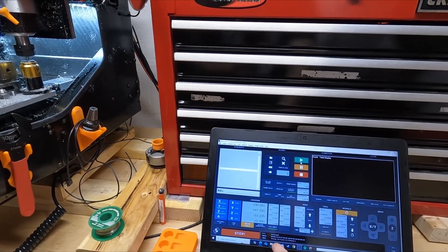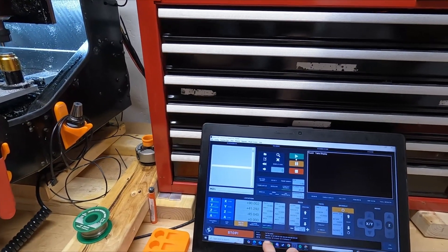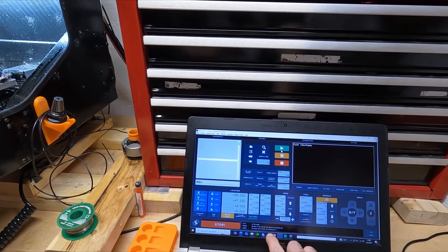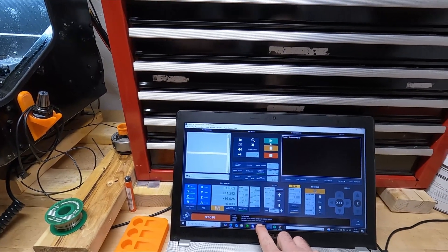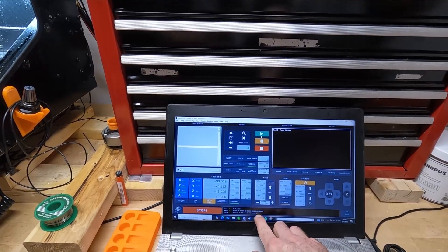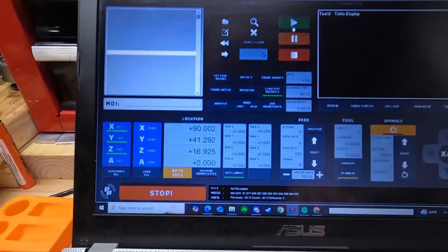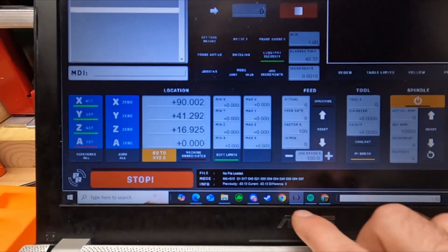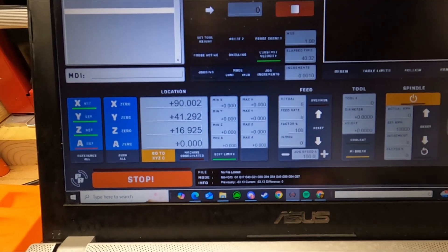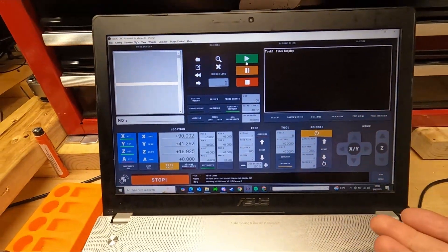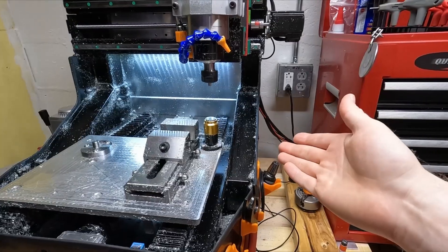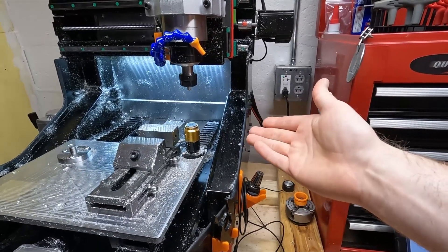We see the probe light come on, and right down here it says previously negative 83, currently negative 83, difference zero — meaning we didn't actually change the tool in this demo. But that shows exactly how the offset comparison and update works.